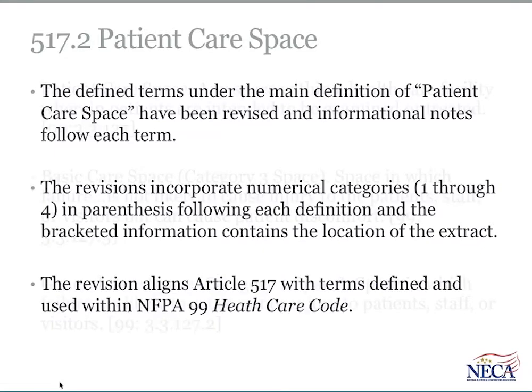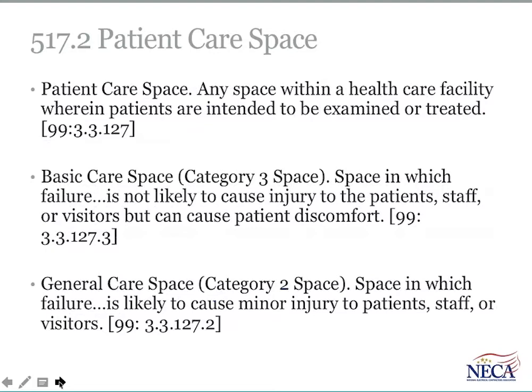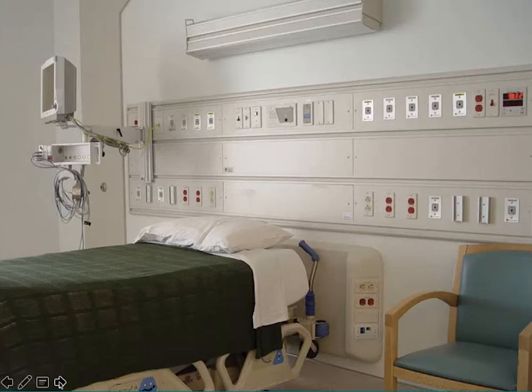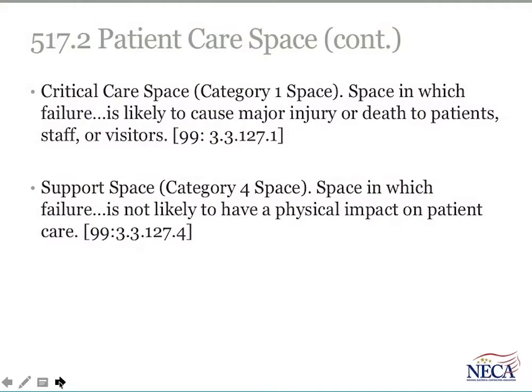Once again, this change aligns with the parent document, NFPA 99. There you can see patient care space. You've got basic care space, which is a category 3. And as the categories go down to 1, you see the level of care, the hierarchy, goes up. We move to general care space, that's a category 2 space, and that would be an example of a category 2 space in a hospital, for example. And then you get into critical care. This is category 1. This is the most critical. These are spaces in which failure is likely to cause major injury or death to patients, visitors, or staff. And then there's support spaces, which has a category of 4.